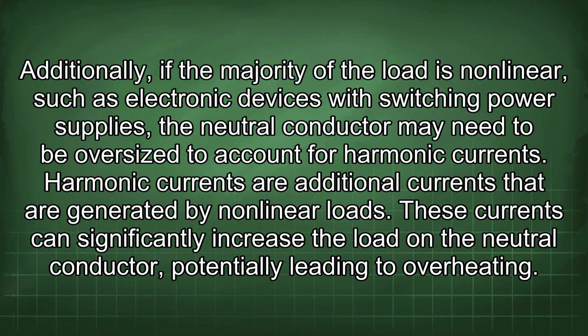Additionally, if the majority of the load is nonlinear, such as electronic devices with switching power supplies, the neutral conductor may need to be oversized to account for harmonic currents. Harmonic currents are additional currents that are generated by nonlinear loads. These currents can significantly increase the load on the neutral conductor, potentially leading to overheating.